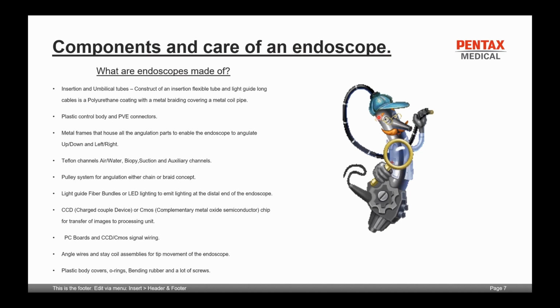You've got a pulley system that enables your scope to angulate. Some scope manufacturers are made out of chain. Some scope manufacturers are made out of a braid. You've got light guide fiber bundles or LED light to emit the lighting at the distal end of the endoscope. You've got a CCD, which is your charge coupled device, or now the CMOS technology, which is a complementary metal oxide semiconductor chips to transfer the images to the processing unit. You've got PC boards, as well as CCD and CMOS signal wires running through your endoscope.